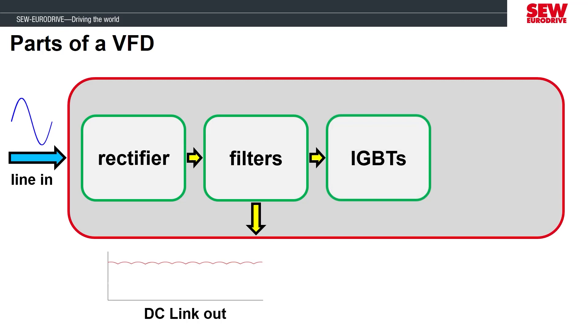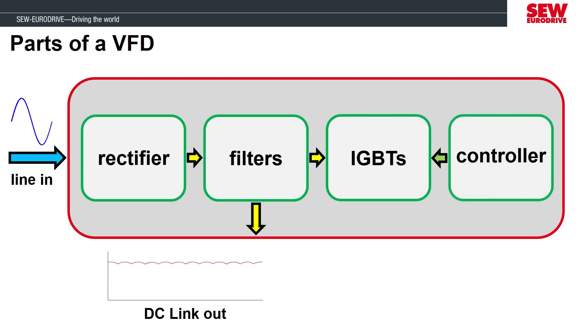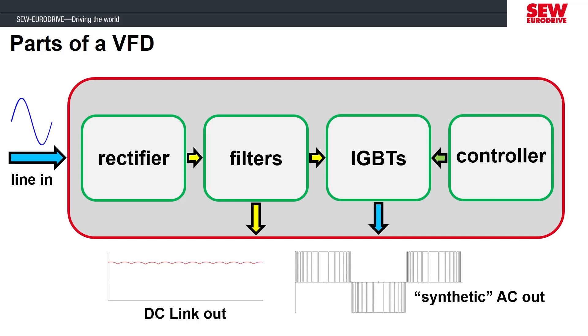To make this DC voltage useful, it is routed to IGBTs — Insulated Gate Bipolar Transistors — which can be simplified as a high-speed electronic switch that can carry a lot of amps. A microcontroller commands the switching of the transistors in a specific timing and sequence pattern. The output of the transistors produces a synthetic or simulated AC output voltage that has positive and negative peaks just like a normal AC supply, so the motor behaves just like it was powered by a normal AC supply.